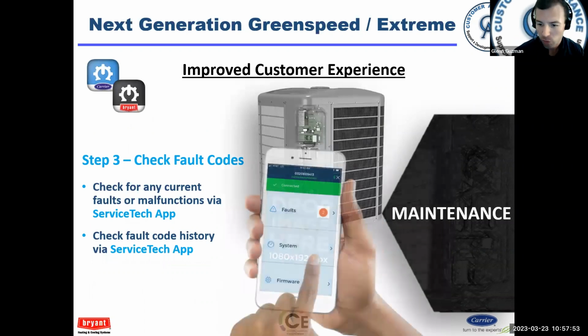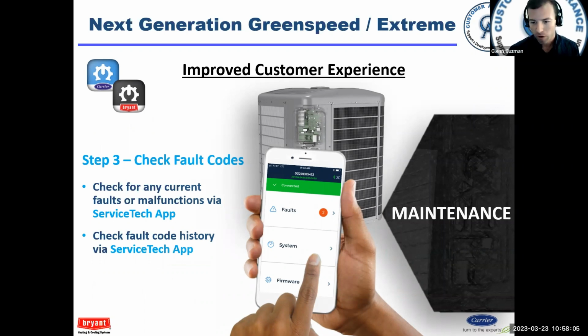Look for current and historic fault codes. Remember, the homeowner said it stopped working the other day and then recovered and was working again. So at that point, I'm going to look at the history and see. Hey, guess what, there was a fault, and maybe I can investigate it now and take a look and see what's going on and get it corrected. Because that's the worst, have a maintenance customer, you do a maintenance, and then there's a callback, it's not working, oh no, what happened? So you always want to be pretty thorough on your maintenances.